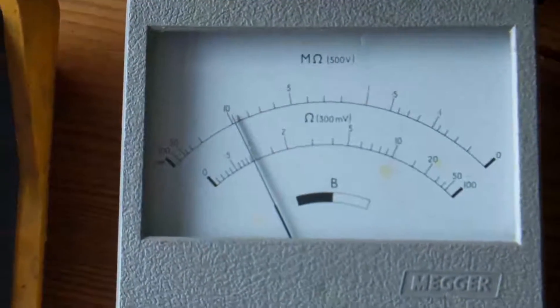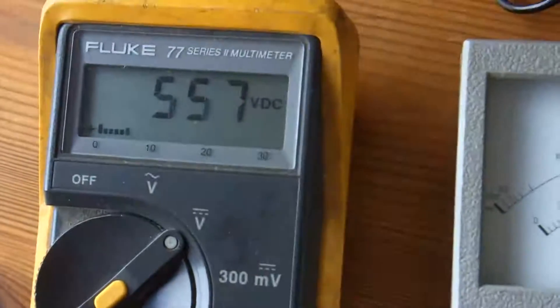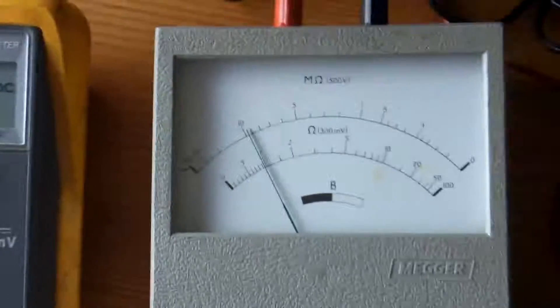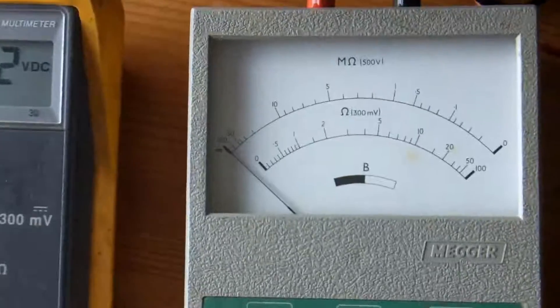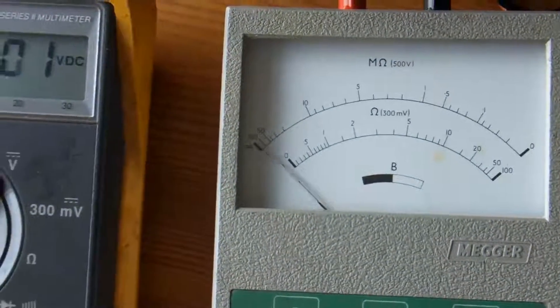A little bit marginal, but if the battery is in the white mark on the meter, then it will produce 500 volts. And it checked out okay on the low ohmic range. Not desperately accurate, but plenty adequate for what the meter is intended for.